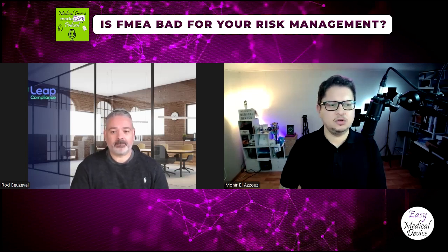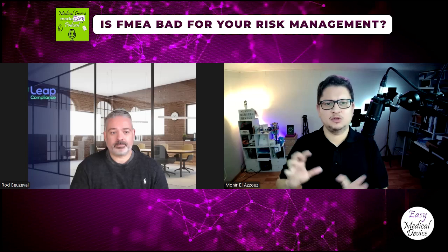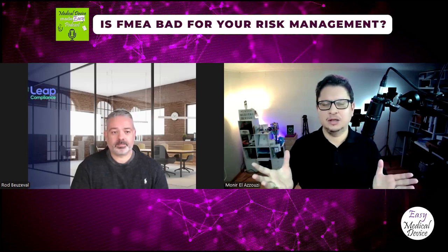Okay, so to summarize a bit, we can use whatever method we want. Maybe we have to customize it to fit the requirements of ISO 14971. Using it as is may not be the right methodology because it doesn't contain all the information. And we really have to understand ISO 14971 so that we can make the best out of this tool.